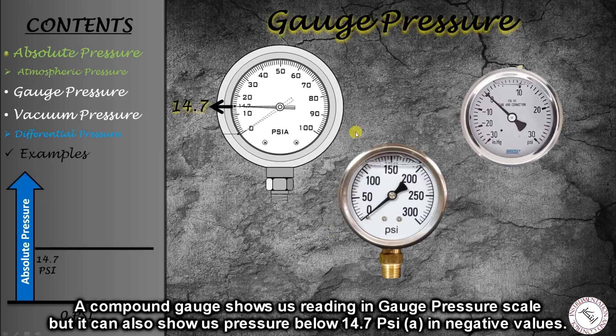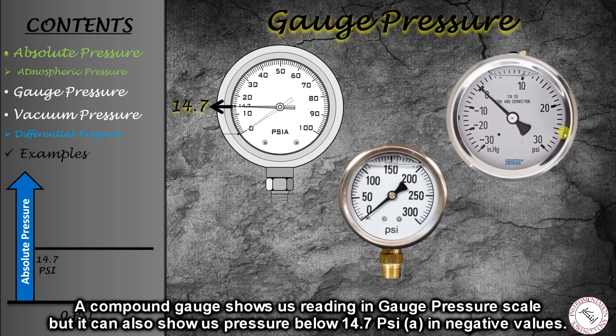There is another type of gauge called a compound gauge. That gauge measures gauge pressure but can show readings both above and below atmospheric pressure. If pressure is below atmospheric pressure, the compound gauge will show negative values. It still uses the gauge pressure measurement scale.